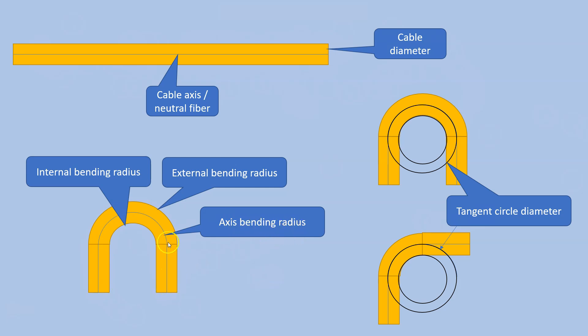That's called the axis bending radius — the bending radius at the axis of the cable. Then we have the internal bending radius, which is the bending radius on the inner side of the cable when bent — the smaller radius. We also have the external bending radius on the outside of the curvature. The external is least used; the most used are the axis and the internal. The bending radius is essentially the radius of a circle tangent to the curvature at that point.